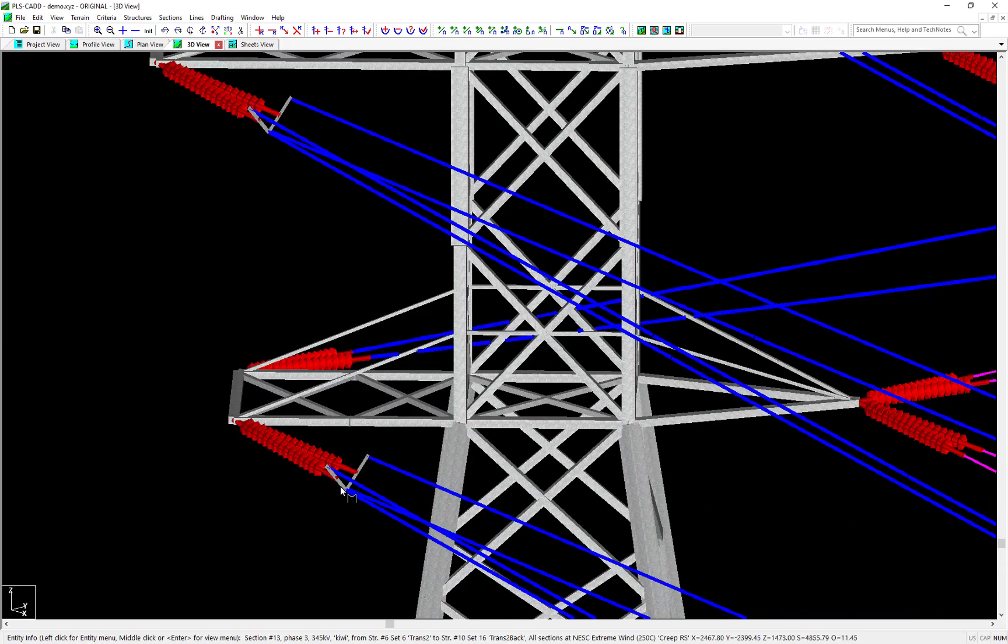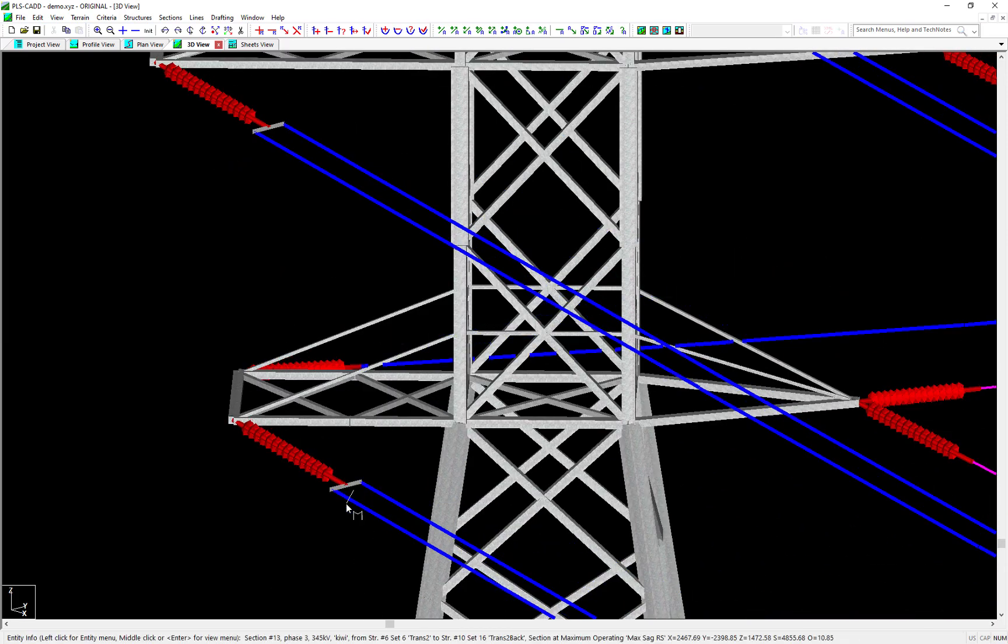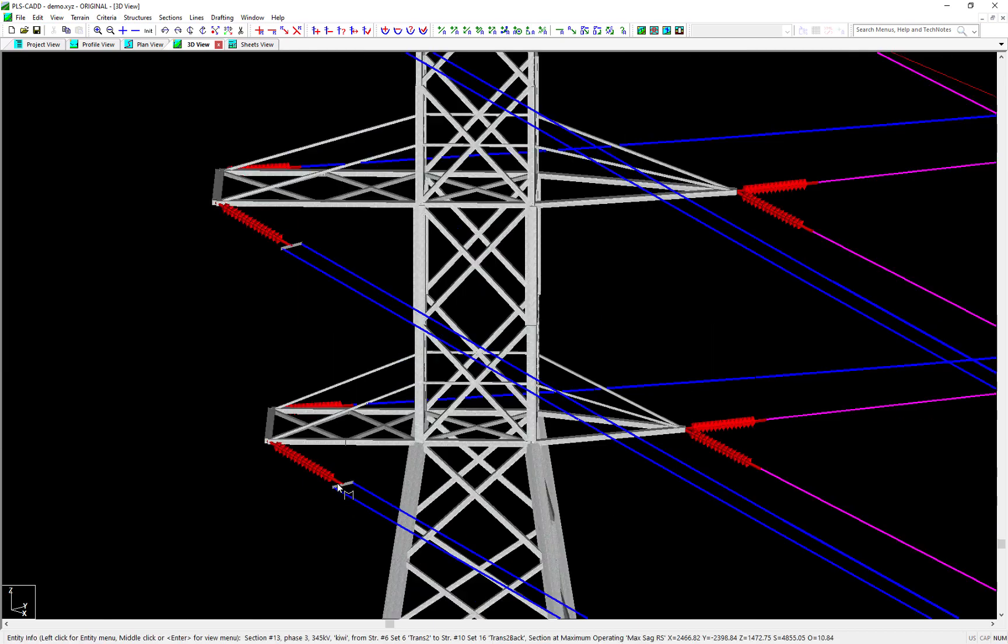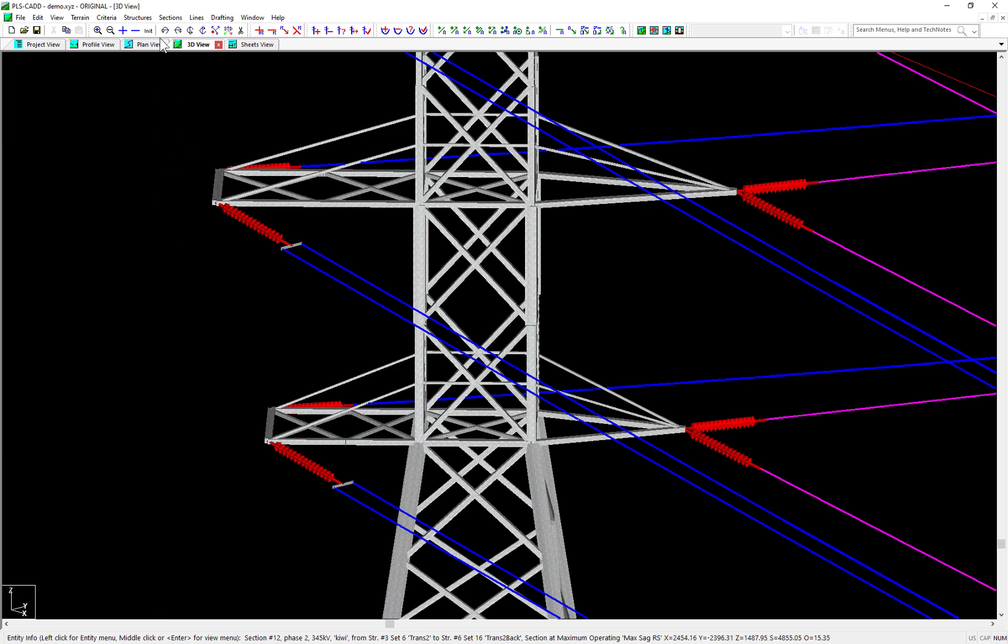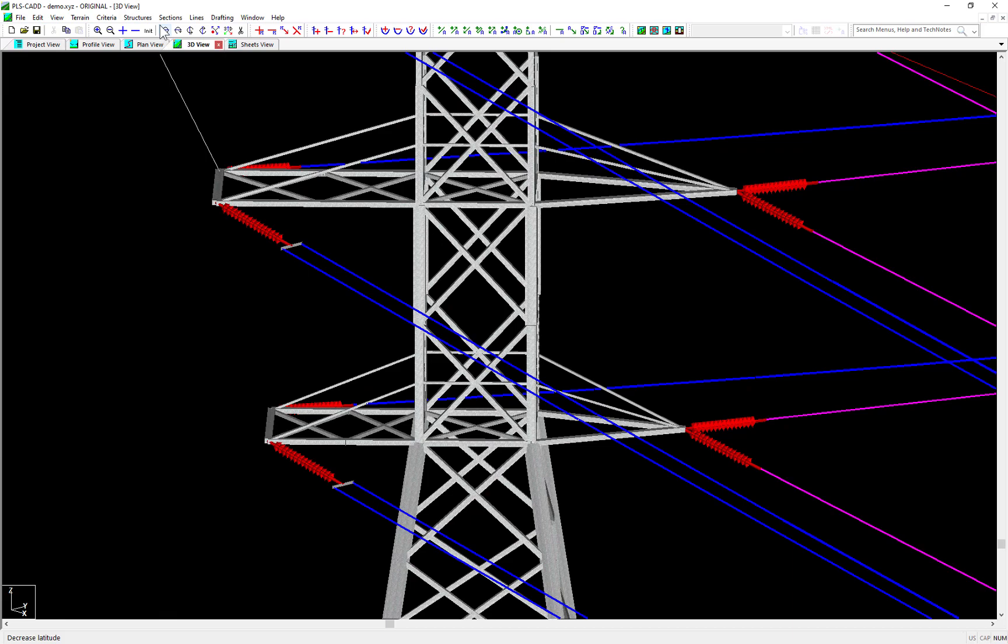For checking clearances from wire to wire or wire to structure, the subconductor geometry is now also automatically being accounted for. Because of the many nuances and uncertainties that can occur within a subconductor geometry, PLS-CADD takes the simple conservative approach by assuming an energized circle around the centroid of the bundle equal to the size of the bundle diameter.